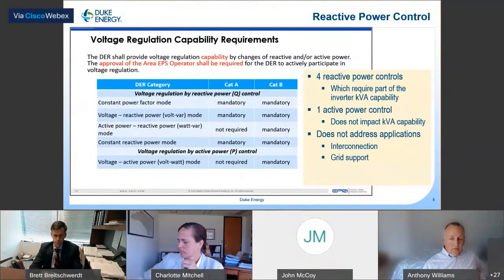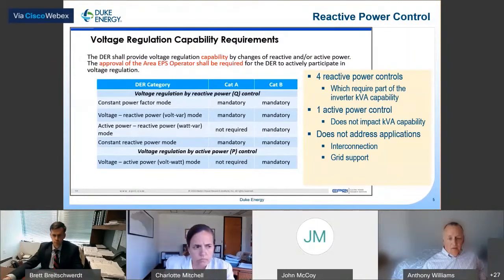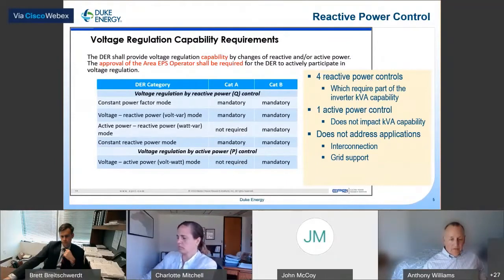Although the table's a little bit busy, it comes right out of the standard, but I wanted to call your attention to the right-hand column for category B, which indicates that all the voltage regulation functions are mandatory with that classification of control. So at the top of the table, there are 4 reactive power controls. And so to inject or absorb reactive power, that does require some of the kVA capability. So in some cases, depending on how the equipment or facility is designed, that can impact the overall active power generation. The last controller is active power control, and you would not expect that to impact the kVA capability.